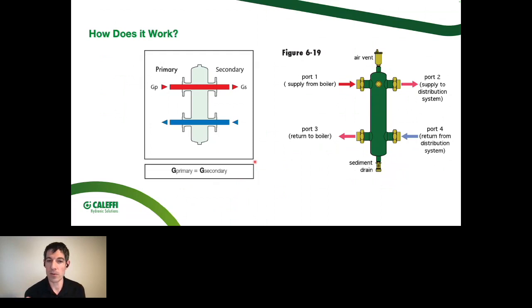If anybody has an example of where you could be right that we don't need to have two different circulators or more, we just need kind of straight pipe from the boiler out to the system and back. So I'm going to give you one, and I'll wait for some answers in the chat if anybody has another one. Let's say we have a snowmelt boiler and just one enormous zone of snowmelt. So the conditions are the snowmelt is off or the snowmelt is on. It's a 0 or a 1 here. We don't have a bunch of different flow rates possible on this side, a bunch of different flow rates possible on this side. It's either on or it's off.